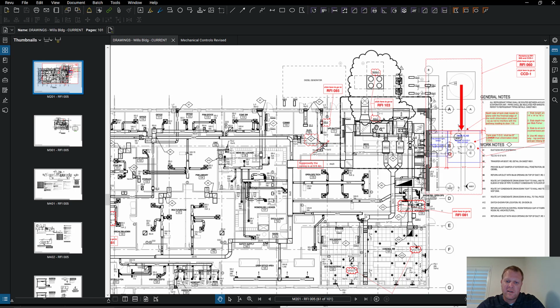The chiller is one component, because what he really wanted to do was provide cold air from the air handler to the rest of the building. He was trying to cool the building because it was going to get hot, and he didn't want to be putting in cabinetry and finishes like carpet in a really hot space that needs to acclimate and be somewhat conditioned. So he was asking, when are you going to start the chiller? What he actually wanted was, when are we going to be able to provide cold air from the air handler to all this space? Very different questions, because the chiller is a component in a larger system, and he was asking about that one specific component.